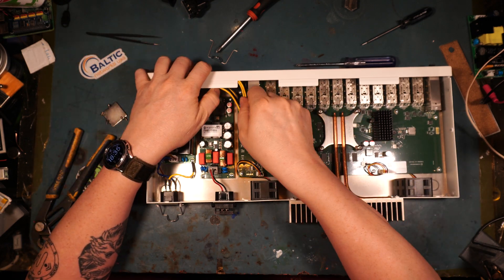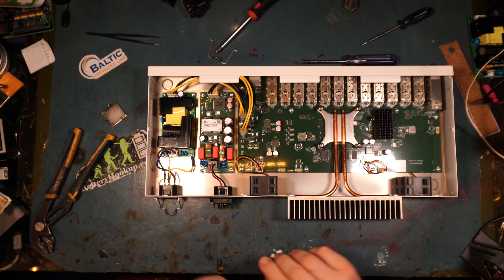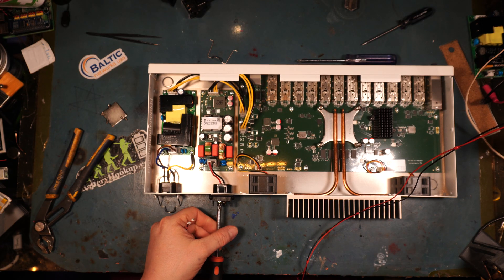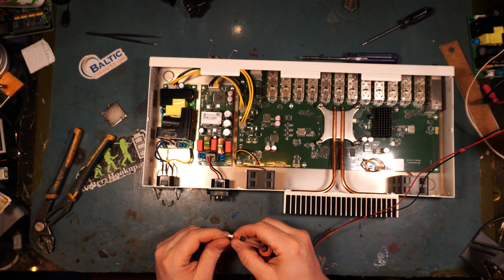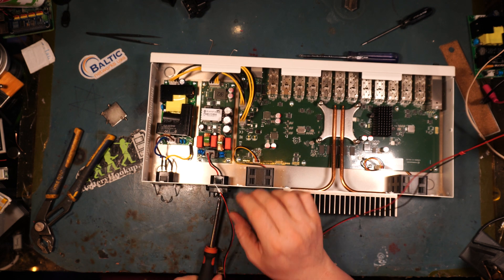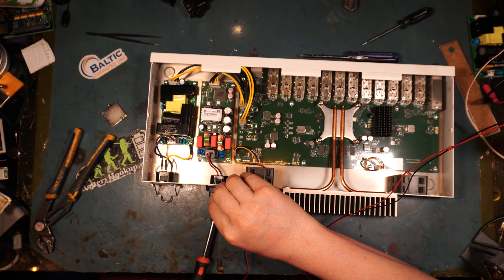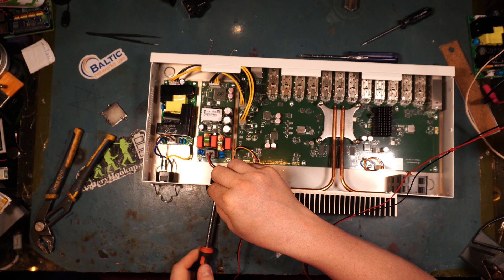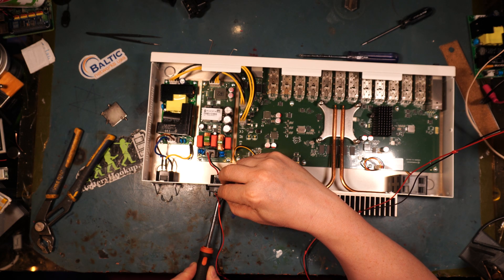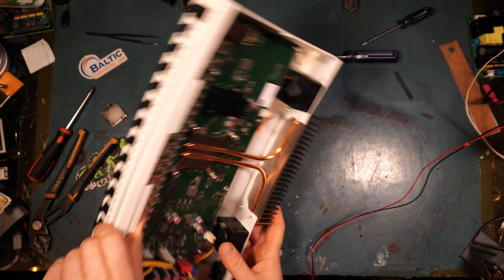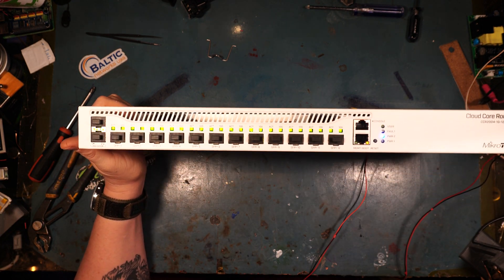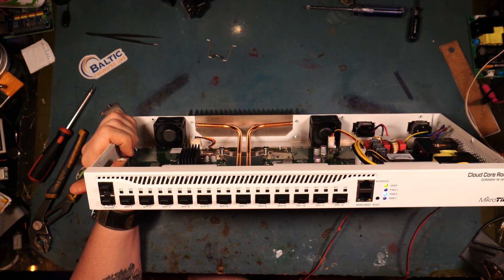Okay, so now that's basically done. Now, of course, before I actually go to seal this thing back up, I'm going to pop this off, and I'm going to grab my test leads here. I've got it set for 54 volts, 3 amps. There is an actual positive and negative indication on here, and by the way, just because the site is Neg48 doesn't mean that there's not a positive and not negative. There's always a positive and negative, and you can't argue that. That's just DC, because that's polarization, right? That's the flow of electrons. On a 48-volt site, your positive is 0V, and your negative is Neg48, or your return, right? There we go. So this guy's hooked up. Just a little bit OCD, so I'm just going to put that a little bit tighter like so. There we go. Nice. Okay, so this guy's in here, and let's blow it up. Oh, sad face. It didn't explode. No, I'm just kidding. I know you degenerates out there want to see things blow up.